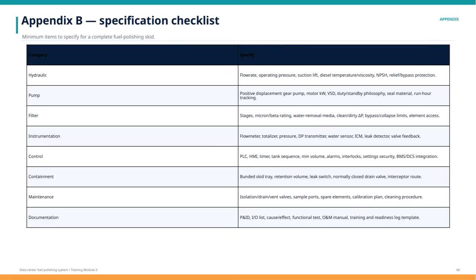Instrumentation includes flow meters, totalizers, pressure and differential pressure transmitters, water sensors, integrated control modules, leak detectors, and valve position feedback. Accurate instrumentation allows for precise monitoring and control of the polishing system. Control specifications encompass the programmable logic controller, human-machine interface, timers, tank sequencing, minimum volume settings, alarms, interlocks, security of settings, and integration with building management or distributed control systems. These control elements are crucial for safe, automated operation and system integration.